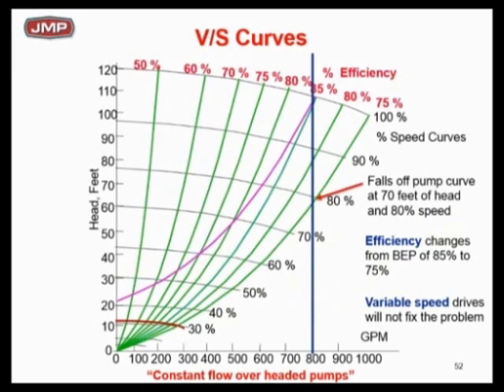What happens if you've over-headed the pump? This is critical — we're seeing major engineering firms make this mistake. You cannot fix an over-headed pump with a variable speed drive and get full flow. The head was specified at 110 feet, 800 GPM, but what if my actual pump head required is only 70 feet? You've over-headed it significantly. If the requirement is only 70 feet and you need that much flow, look at the blue line.